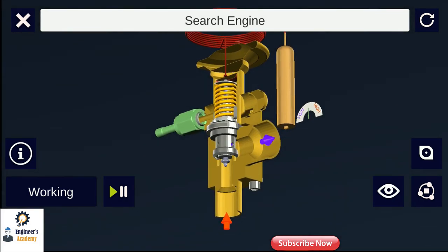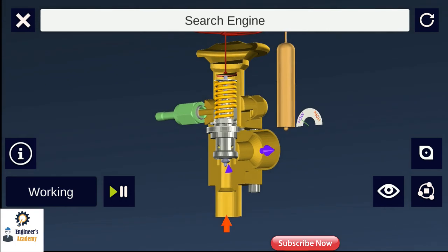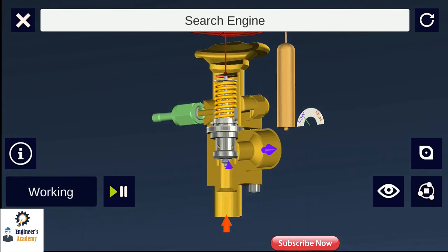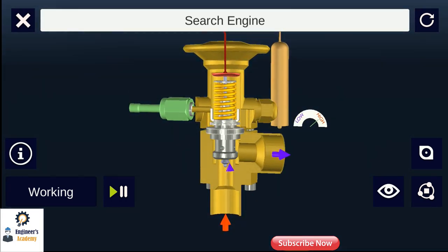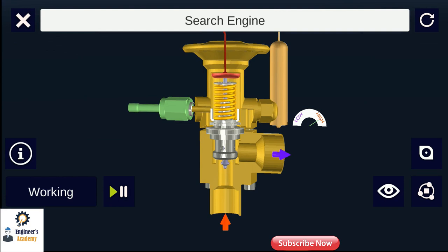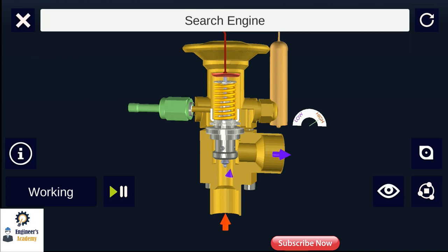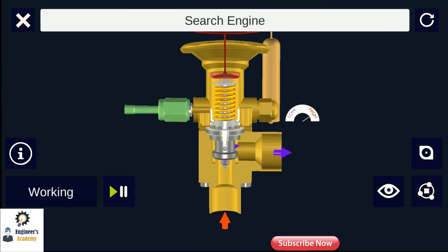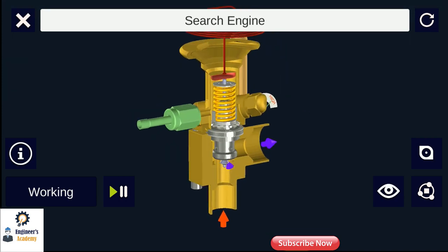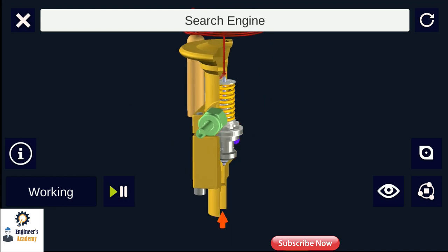As the refrigerant passes through the evaporator and is exposed to more thermal energy, it will undergo a complete phase change and will become a saturated vapor towards the end of the evaporator coil. The refrigerant will continue to pick up thermal energy, and when it does this after the phase change, it will then start to increase in temperature. This superheats the refrigerant vapor.